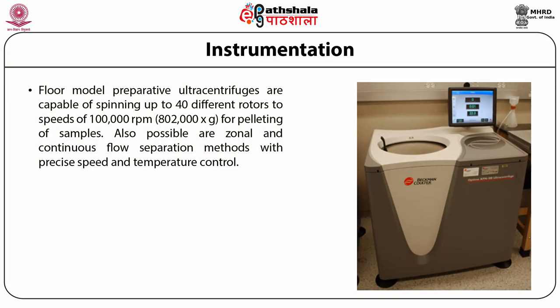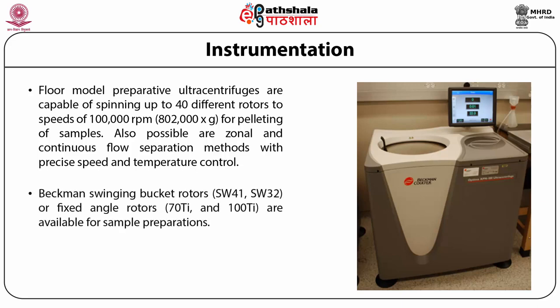The Floor Model Preparative Ultracentrifuge is capable of spinning up to 40 different rotors to a speed of 100,000 rpm, equivalent to 800,000 g, for pelleting of samples. Zonal and continuous flow separation methods are also possible with precise speed and temperature control. Beckman swinging bucket or fixed angle rotors are available for this type of sample preparation.